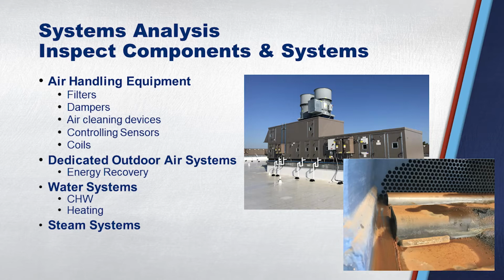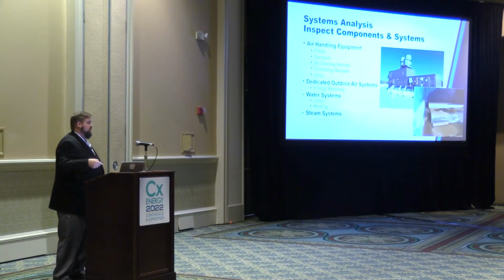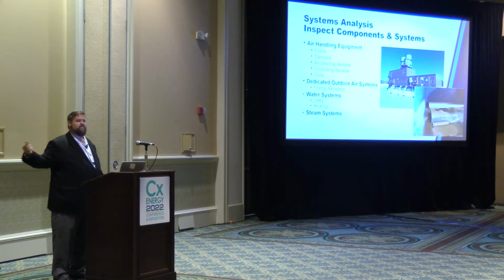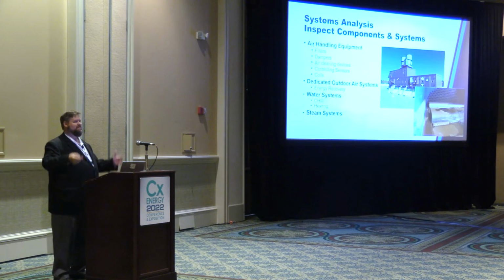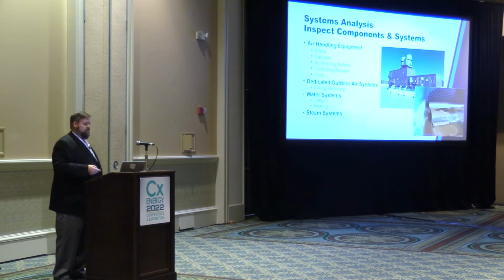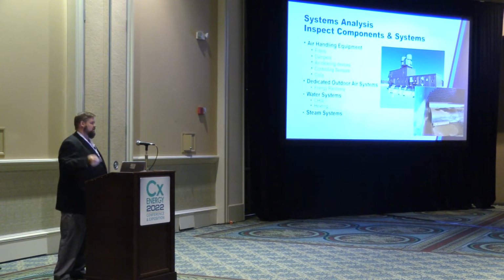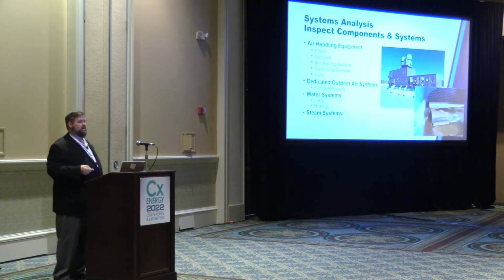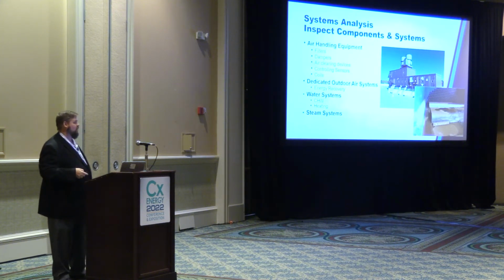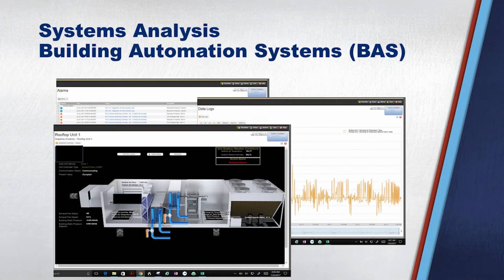I also say look at your water system. In the beginning some of it comes down to energy, but a lot of people were leaving their buildings and either letting everything run, or turning everything off. We had one client turn everything off, and in 2.5 months the chiller fouled up - they had to punch down the tubes because they didn't run the water and the water treatment went away. So those are things to think about for the future, for next time.